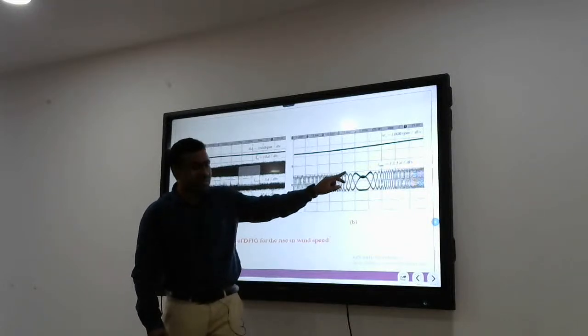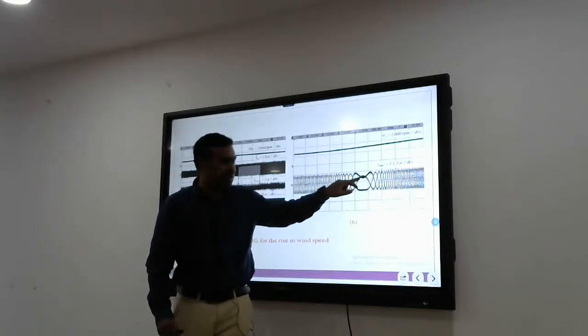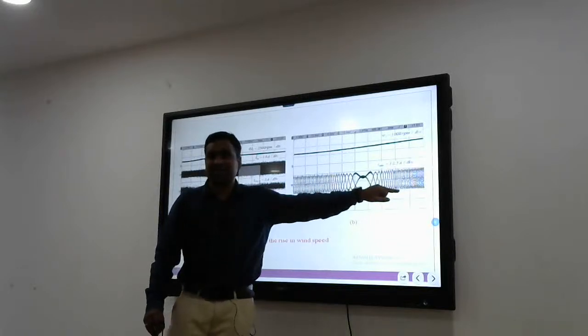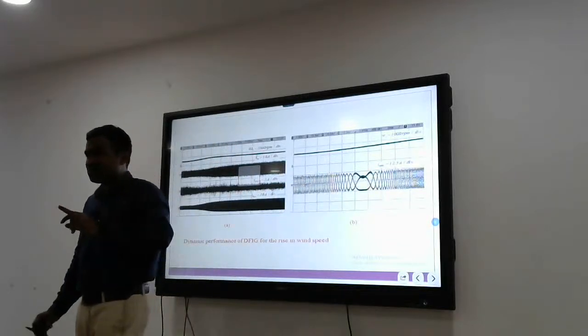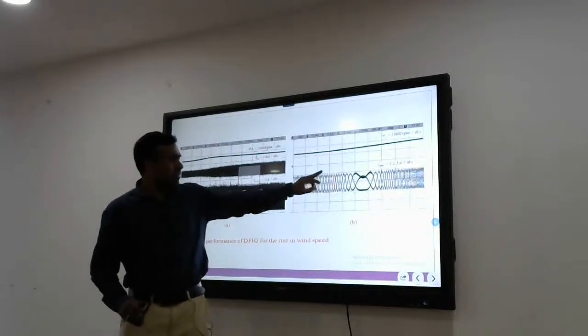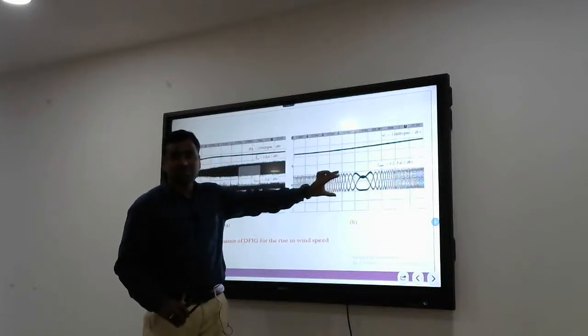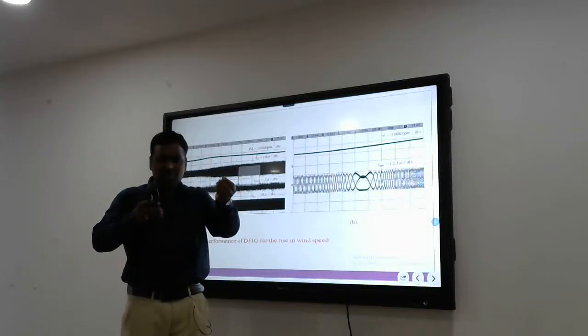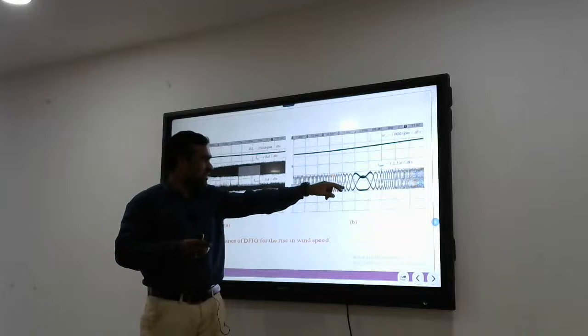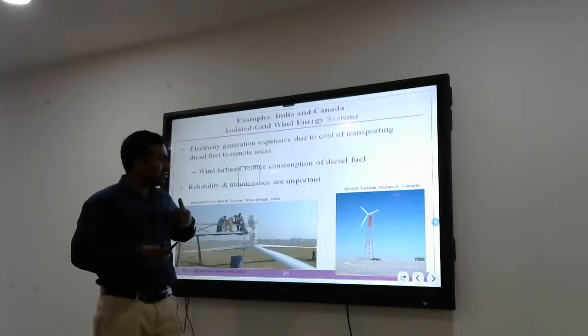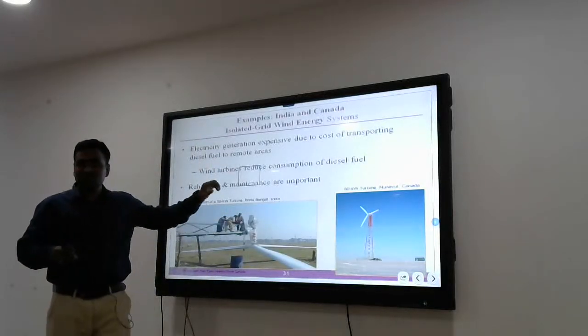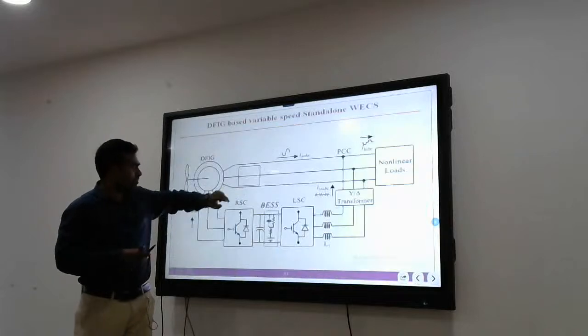So for getting reverse power, the current direction was reversed. Previously ABC was there, now it has become ACB. Now one of the currents has changed its direction, from ABC to ACB, and now the power will be reversed. These were captured using an oscilloscope. The real rotor currents of the machine were sensed. This is standalone. I'll quickly go through.